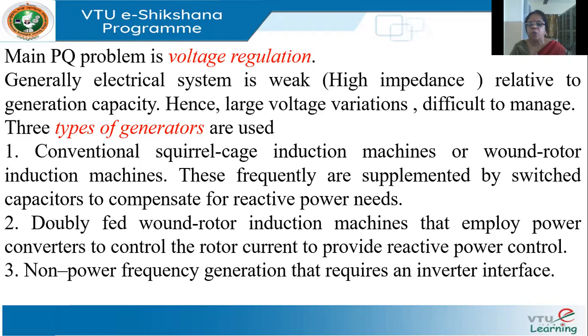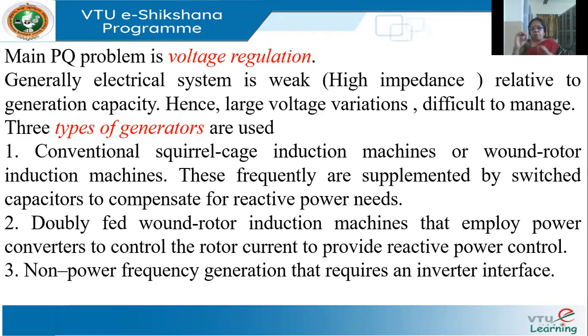Recently, doubly fed induction machines — called DFIGs (doubly fed induction generators) — are becoming popular. They use power converters to control the reactive power. Non-power-frequency generation can also be used, which requires an inverter interface to connect to the grid. Wherever we have wind farms, there are power electronic devices present, and apart from voltage regulation, these can also cause harmonic problems.